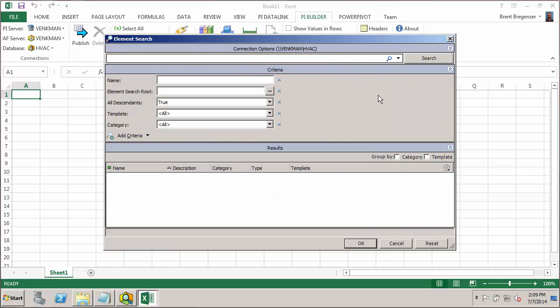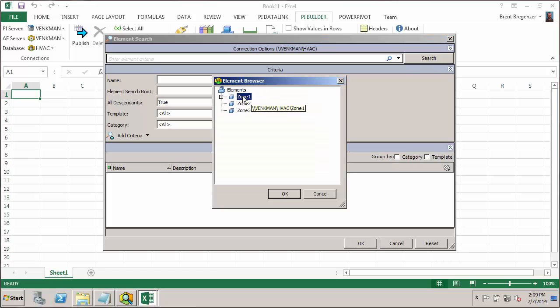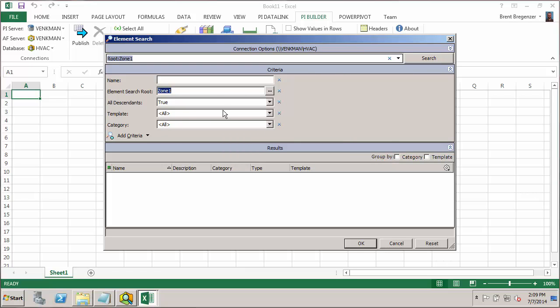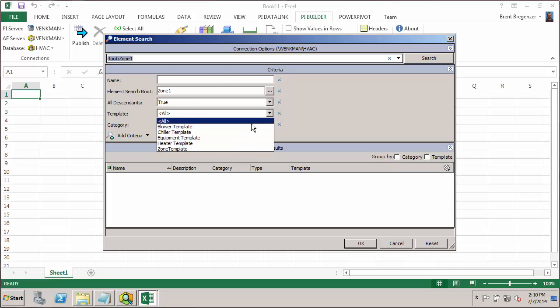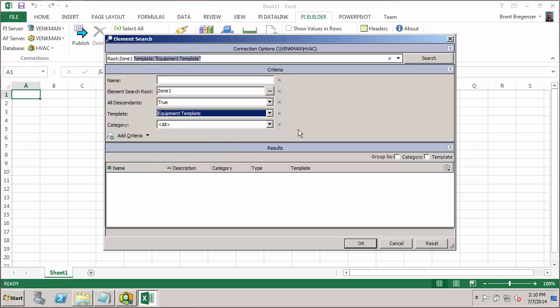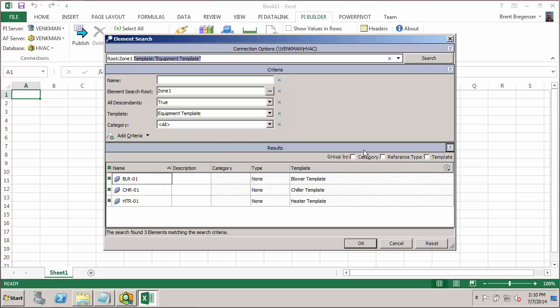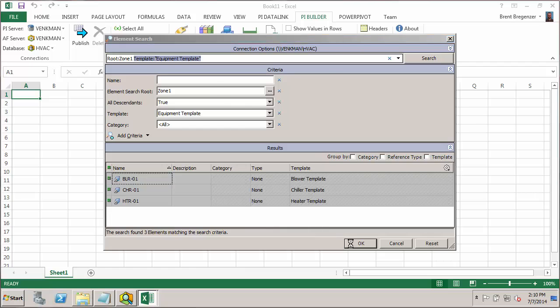This works very similarly to the one in PI System Explorer. It just looks a little bit different. So we'll want to start by specifying a root element to search in. I'll search with Zone 1 as my root since the three elements I want appear under that zone. And then I could go into Name and do some sort of name search like star-01 since I know that all the names end in that. Or I could go into Templates and since I know they're all based off the same parent template of the element template, I can select that and that should turn up all the elements I'm looking for. So there we go. I got my three elements that use Equipment Template as their base template. And I'll select all three of those and import them.